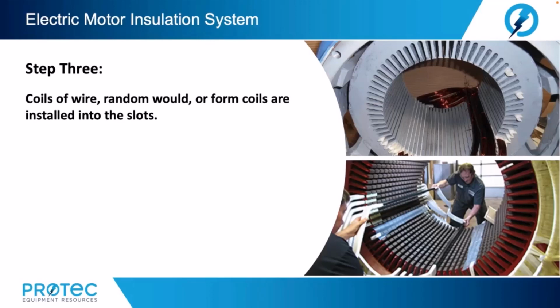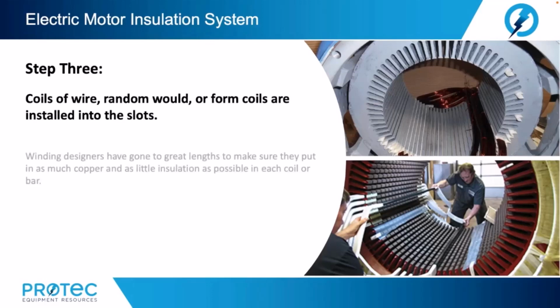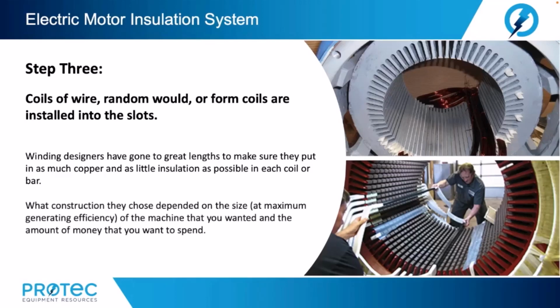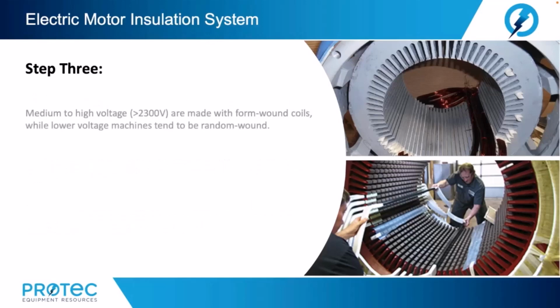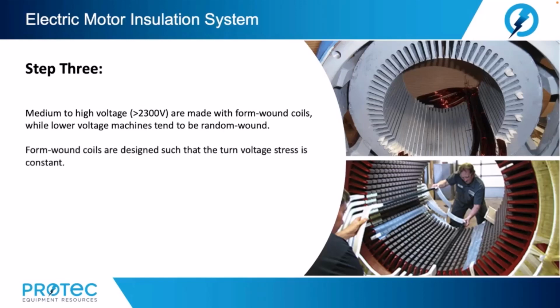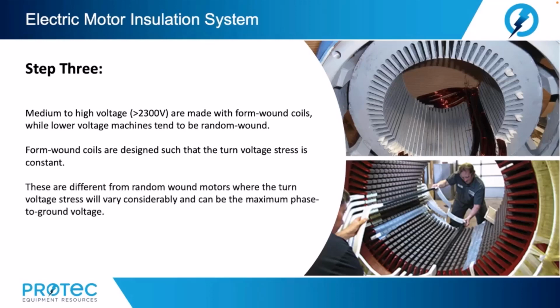In step 3, coils of wire, random wound or form coils, are installed into the slots. Winding designers have gone to great lengths to make sure they put in as much copper and as little insulation as possible in each coil or bar. What construction they choose depends on the size, at maximum generating efficiency, of the machine that you want and the amount of money that you want to spend. Medium to high voltage, greater than 2300 volts, are made with form wound coils, while lower voltage machines tend to be random wound. Form wound coils are designed such that the turn voltage stress is constant. These are different from random wound motors, where the turn voltage stress will vary considerably and can be the maximum phase to ground voltage.